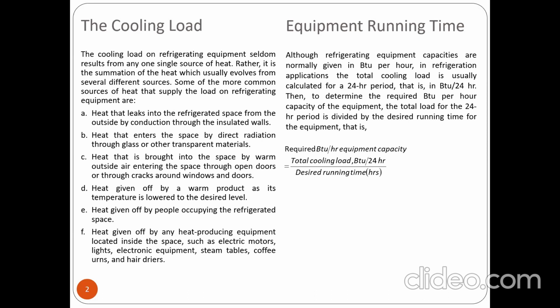A, the heat that leaks into the refrigerated space from the outside by conduction through the insulated walls. So, may init siya. Kasi may insulation siya, hindi mag-zero yan. Okay? B, the heat that enters the space by direct radiation through glass or other transparent materials. Kung meron kang sa cold room mo o sa cold storage mo, meron kasi mga warehouse type na malalaki. So, meron siya mga bintana. C, heat that is brought into the space by warm outside air entering the space through open doors or through cracks around windows and door, yung mga infiltrations.